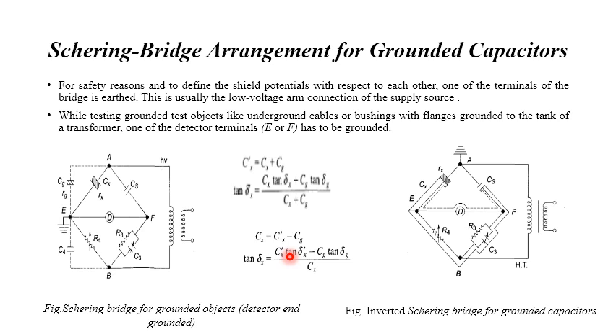Hence the accuracy of the measurement is poor if the grounded capacitance is large compared to the test object capacitance. So care has to be taken. This is the Schering bridge for the grounded capacitance, and this is the inverted one. So you can see this is the parallel combination. With inserting and without inserting, we will get the balance equation, and we are going to find out.